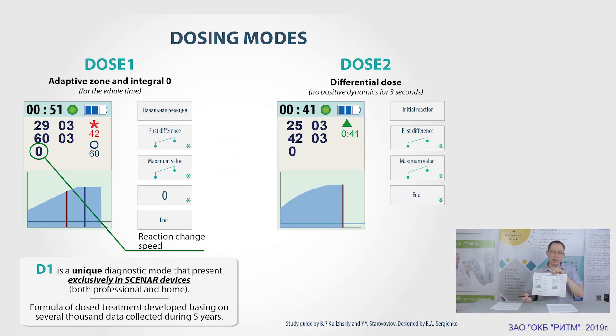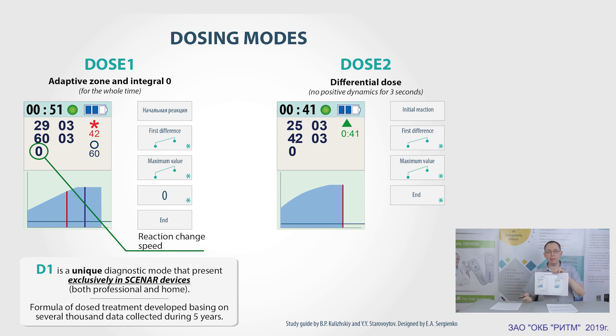The primary expert criterion is the value of reaction. When the electrode is applied to the skin, the value of initial reaction appears and stays on the screen. If we take the device off the skin, this value will remain on the screen. But if we keep it, starting from the second second, there will appear another value, which is dynamically changed and called the current reaction.